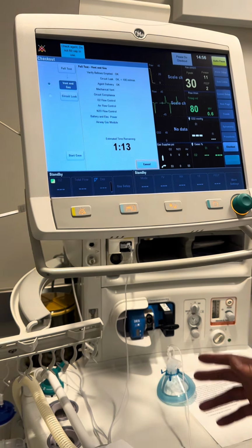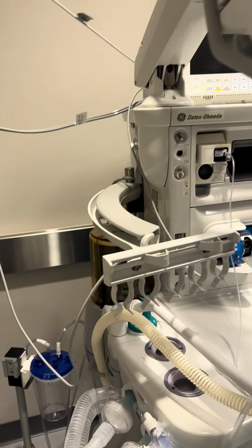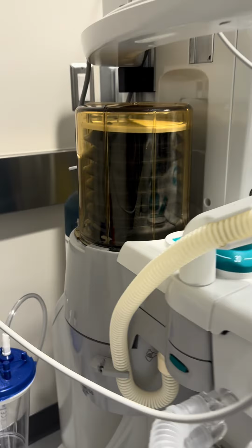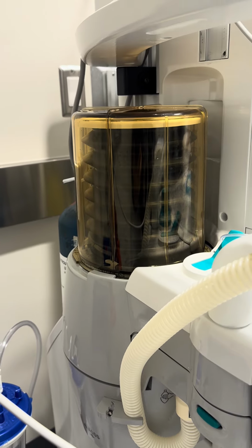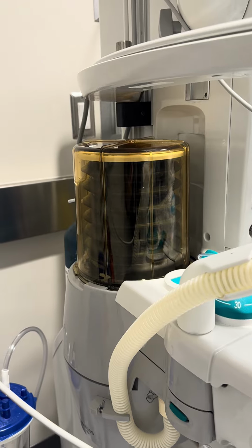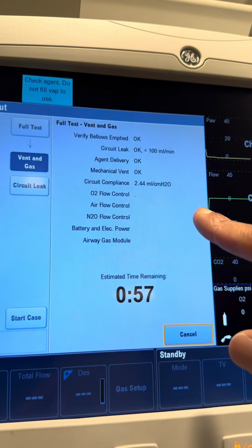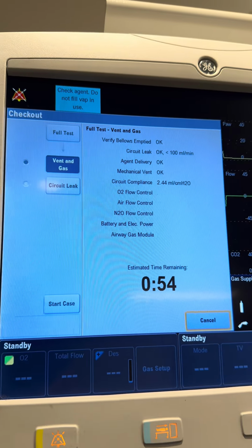So you got the bellows right now because it's checking our agent delivery. So basically the bellows is driving down to make sure that the gases are being compressed into the system. So we're good there. Our circuit leak is good. As you can see, our circuit compliance is 2.44 millimeters or centimeters of water. So that's good to go there.